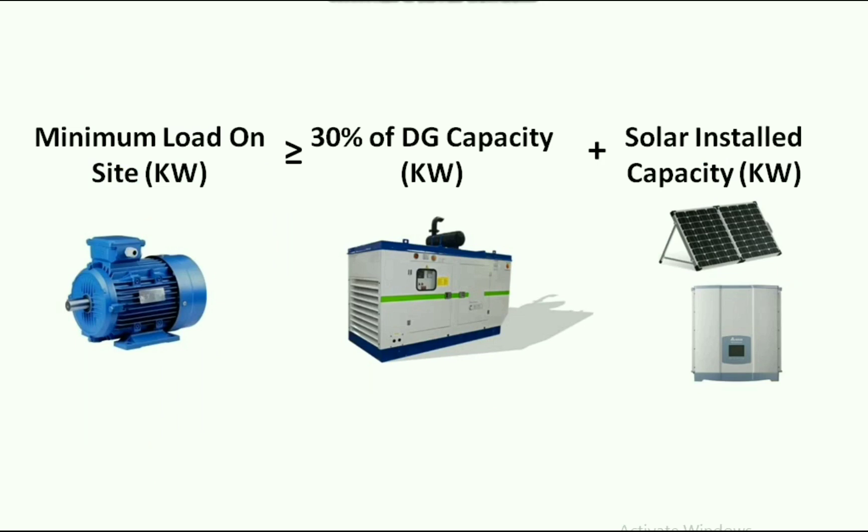We can derive a formula that must be satisfied to sync a DG with solar. The formula is: minimum load on site should be greater than or equal to 30% of DG capacity plus solar plant capacity. If a system satisfies this condition, the DG will sync normally with the solar plant.